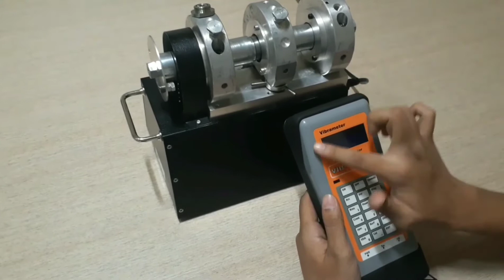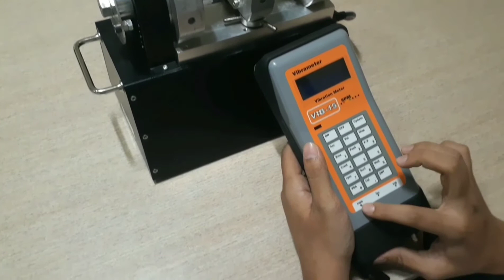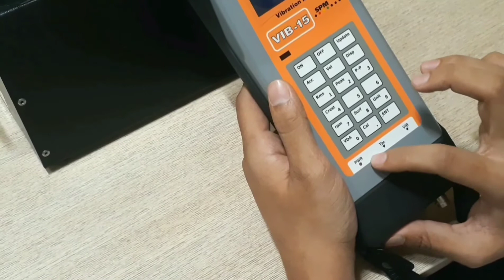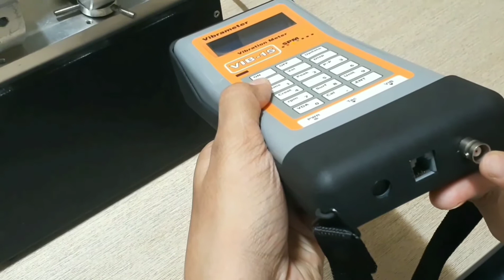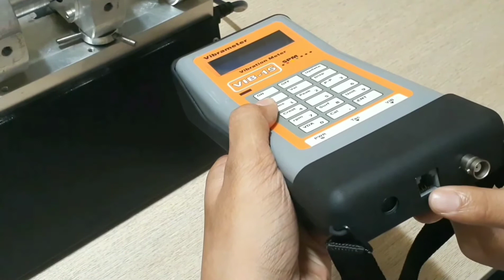As you can see, this is the LCD display. We also have here the peak indicator. Here is the power. When we switch on the instrument, here we will be getting the power indication. This is the tachometer input, and this is for vibration. We can fix here the vibration transducer cable, and here we can fix the tachometer, which is for RPM measurement.